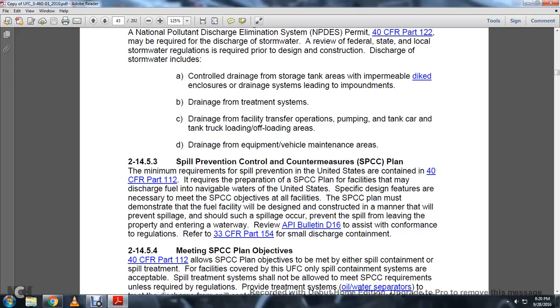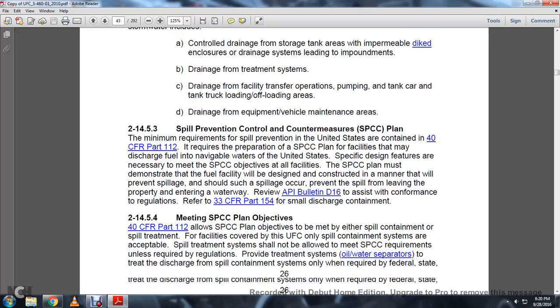The spill prevention control countermeasure plan must demonstrate the fuel facility will be designed and constructed in a manner that will prevent the spillage. If such a spillage occurs, prevent the spill from leaving the property and entering the waterway. Review the API Bulletin D16 to assist the conformance with the regulation. Further, Title 33 CFR Part 154 covers small discharge containment.